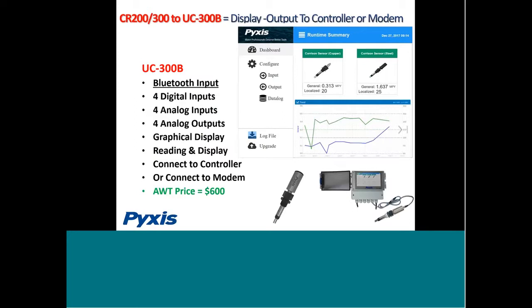And then the same thing on the CR200 to UC300B is just functionality. However, it offers more input. You can connect up to two corrosion sensors for both pitting and general corrosion on one UC300B. And it is a touchscreen interface which will enable you to also connect from that point to a controller.